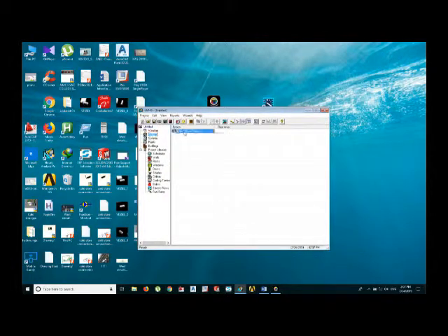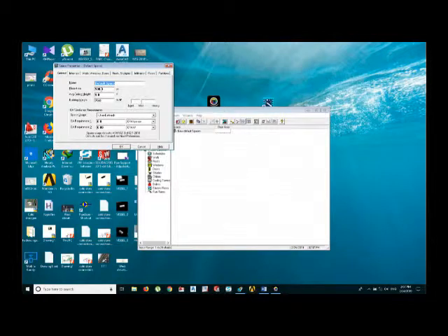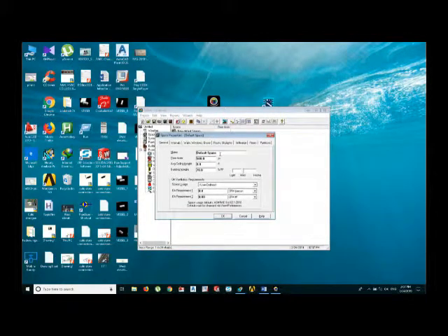Second thing is space. You will define the space, default space, like office. I'm going to calculate the load of an office. My office floor area is 10 by 10, 100 square feet. 9 is the average ceiling height from floor to false ceiling. My building is medium, not that heavy and not light.